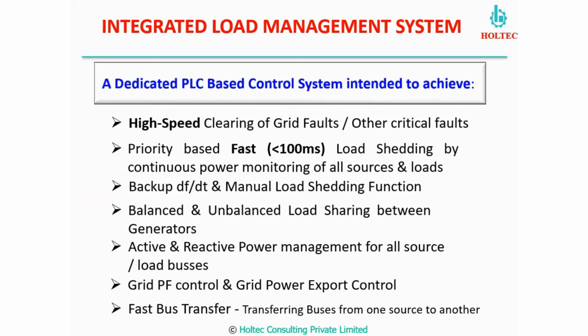Fast bus transfer means we have multiple sources. Now we have a situation where there is an overloading in one of the sources, on which one of the buses is feeding, say a source is feeding power to bus number 1, and its load is increased to the capacity of the source. Then what will happen? Without having any interruption, this entire bus we can shift to another source where we have lesser loading, so that the load on those buses will not be affected. So this is called fast bus transfer scheme. This is also possible through our integrated load management system, which we are actually designing in Holtec.